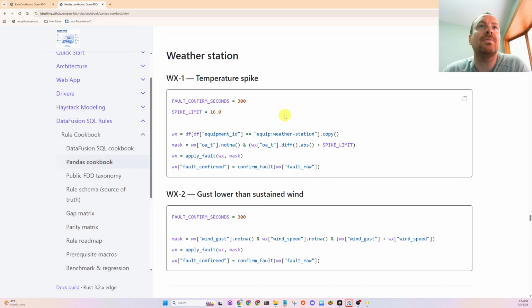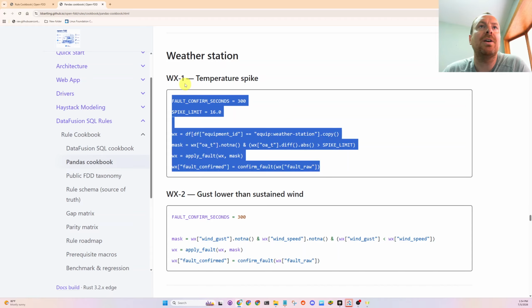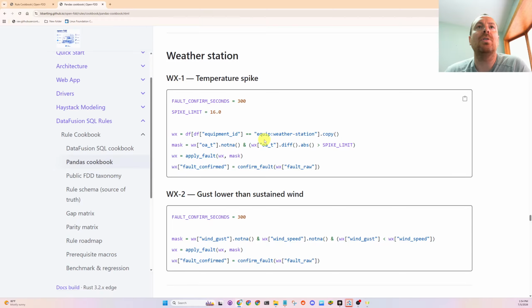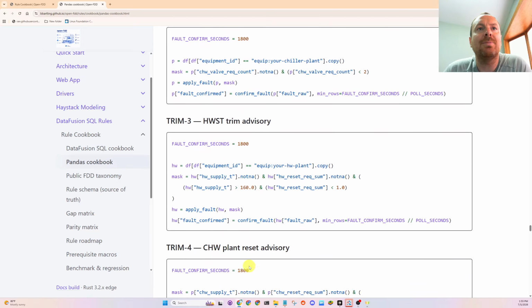Even weather station data, which we should be comparing to local sensors. I'm also doing by default a 300 second, or 5 minute, delay. So when we run the rules across the historical data, there needs to be a 5-minute delay—an adjustable parameter—before flagging something as a true rule. It's like a delay parameter, just to weed out false positives.